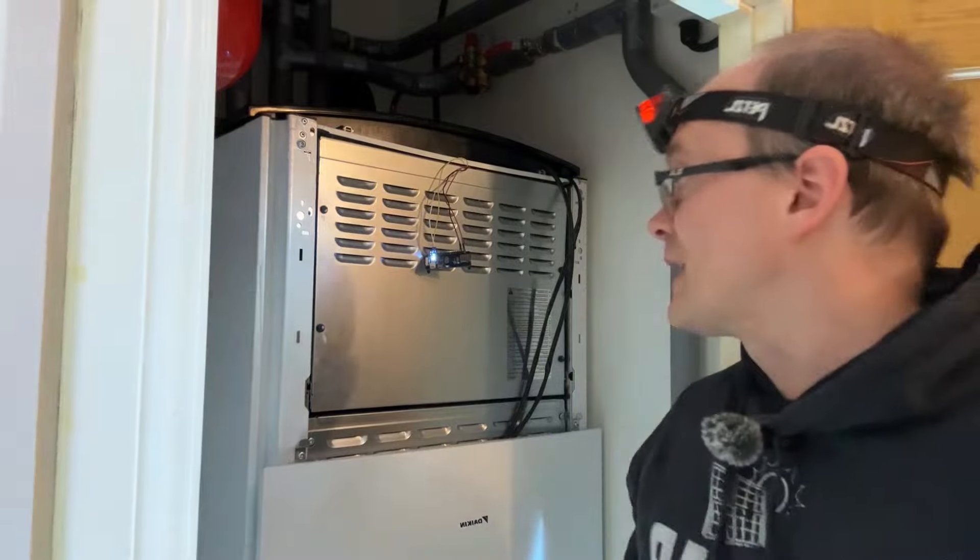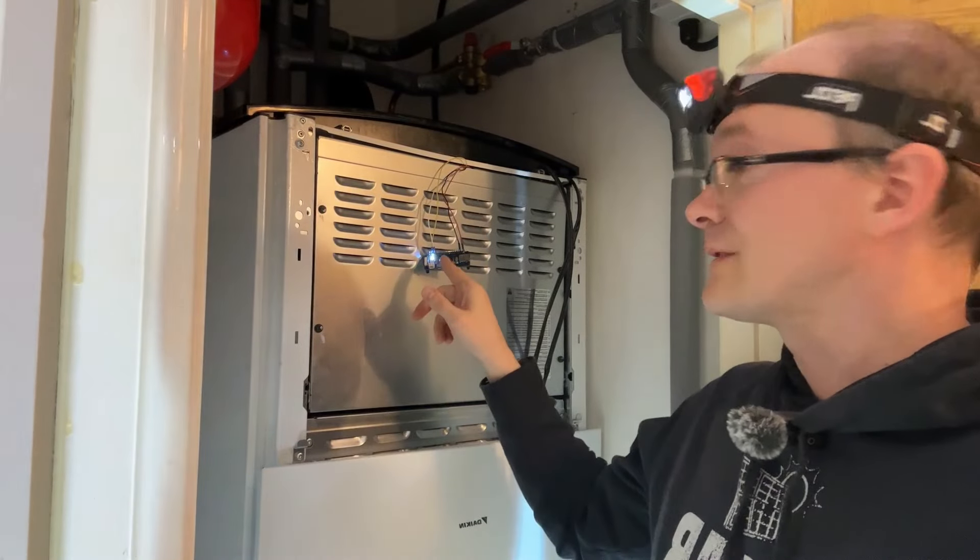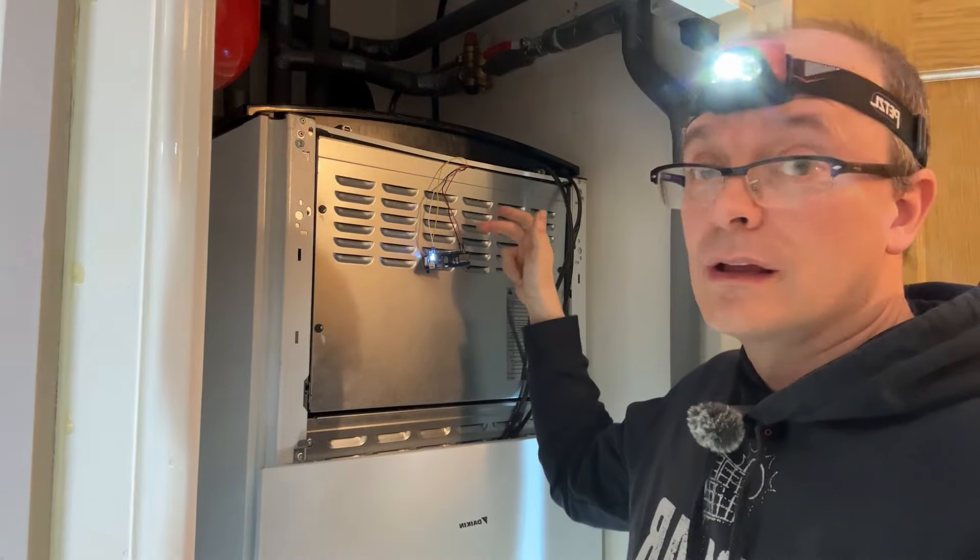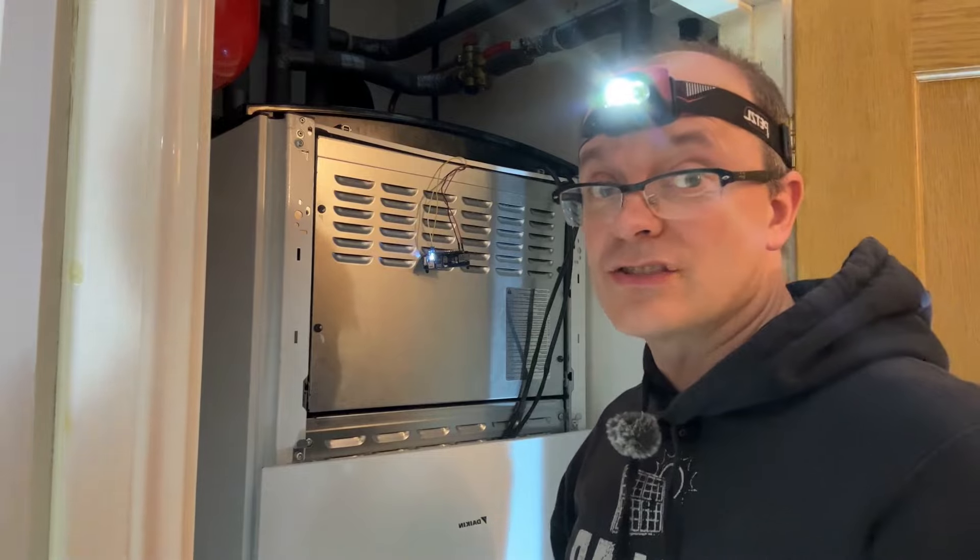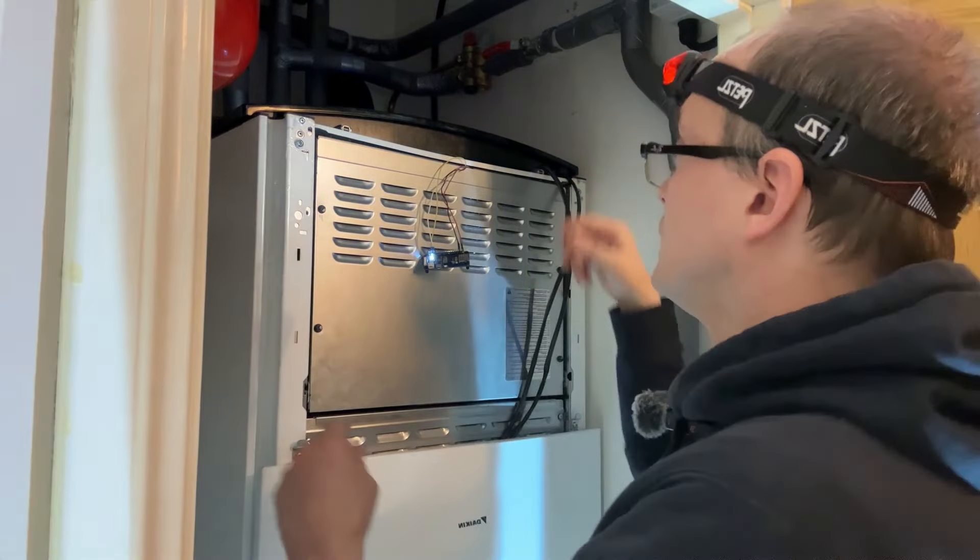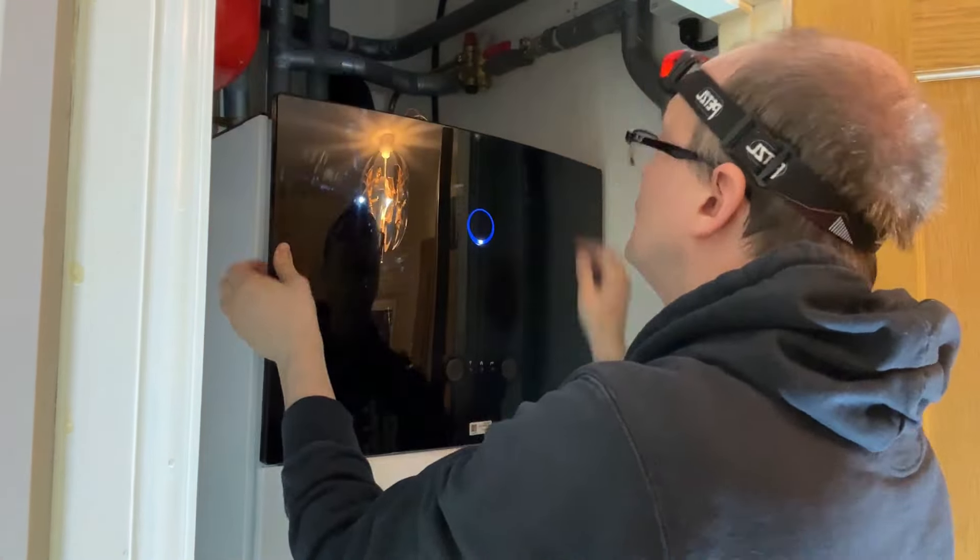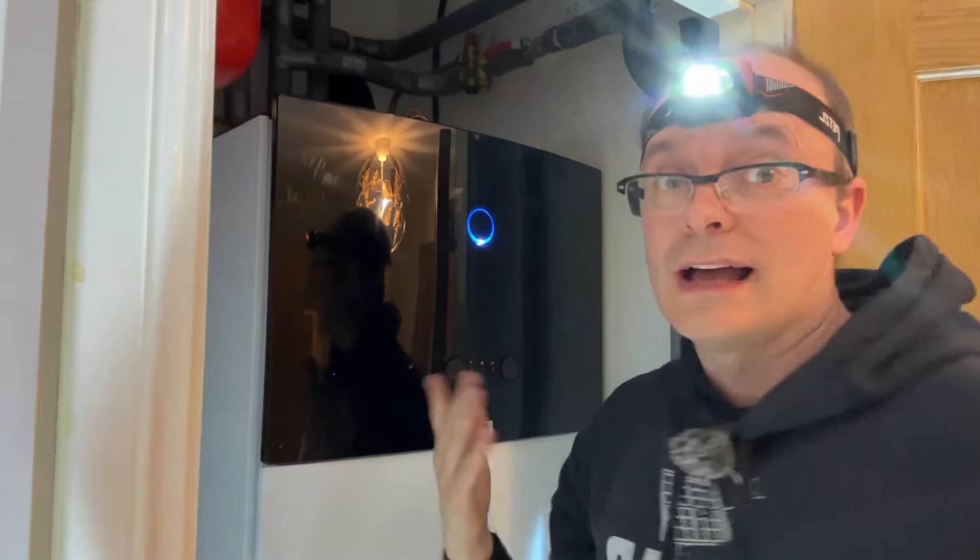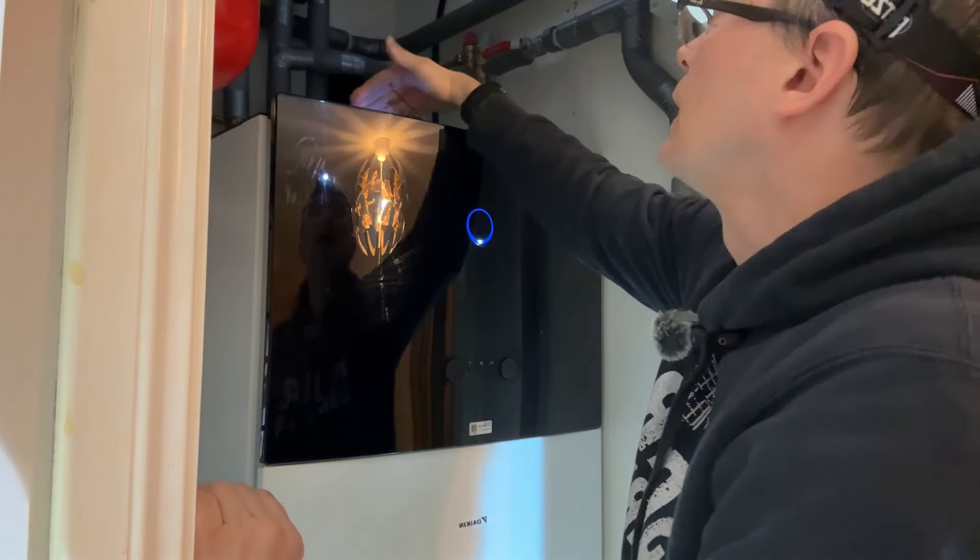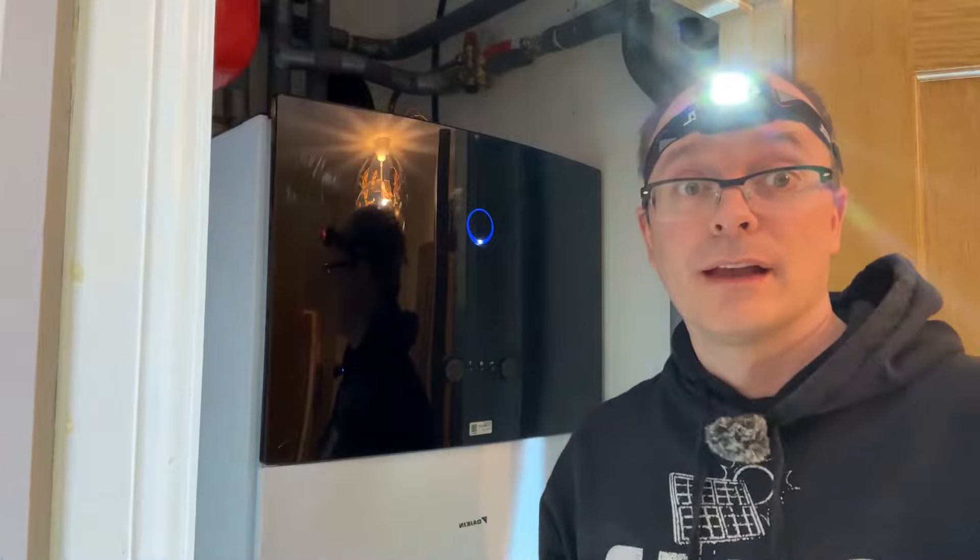So this is now going to be just moved out of the way up here we'll move this cable off to the side like so and we'll open up this hatch here. It's quite warm in here. So here we are. Sometimes you can hear a relay clicking especially when you hook up the 5 volt supply. So let's take a closer look in here. So here you can see we've got a 5 pin DuPont connector connected onto X10A terminal which you can probably just see there. So what we've got we've got 5 volts, the red wire, ground which is the black wire on pin 5 and then we've got pin 2 and 3. Pin 2 is transmit, pin 3 is receive. So this is a standard RS-232 connection.